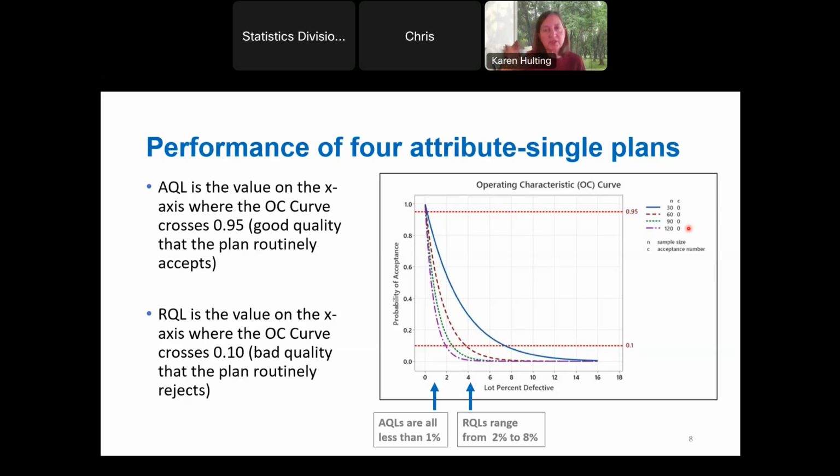We're uncomfortable still shipping product if we've found any defects at all. And so this allows us to only ship when we found no defects at all. Now, the logical problem with that is that just because we saw no defects, especially if we have a small sample size, that doesn't mean there are none in the product, right? It just means we haven't seen them. And so sometimes people are more comfortable than they should be with small sample sizes and accept on zero plans.